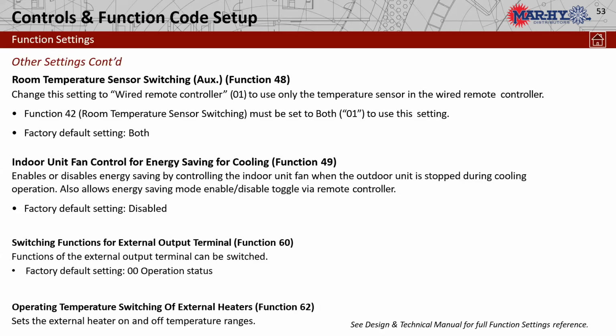Function 60. This is the function that you would use with that external PCB, that input-output auxiliary accessory PCB for fresh airs, dampers, economizers, etc. With function 60, we'll set the parameters on what we want to, are we measuring input, output, what is it we're switching? We'll set that up with function 60 when you're using that external PCB. Then we got function 62. That sets the external heater off temperature range.